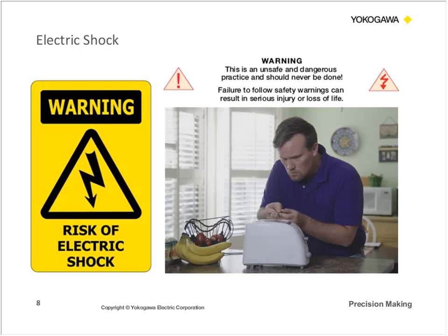So, different discrepancies, but as far as the basic considerations, regardless of the voltage value, the first concern I'm sure most all of us have when dealing with high voltage is the risk of electric shock. Now, in most cases, direct contact with voltages greater than 42 volts will result in bodily harm. So for the sake of today's conversation, we will define high voltage as anything greater than 42 volts. And really, some non-isolated data acquisition equipment will see equipment damage at any direct voltage of 50 volts or higher.